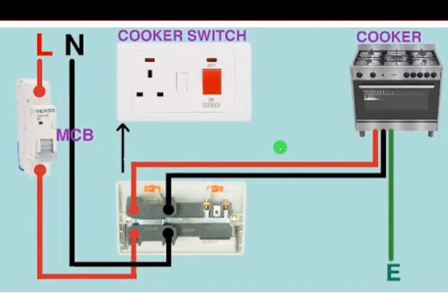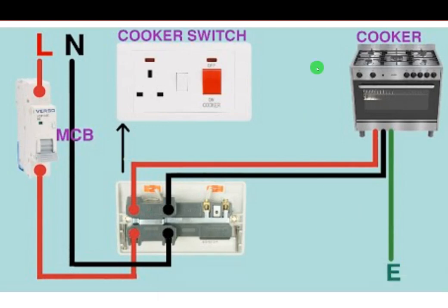Okay, so that is why the calculation is very simple. The 10 amps is because you use an additional auxiliary socket attached. Then the leftover current belongs to the cooker. All right, hope it's clear. So the 10 amps is for here, then the rest is for the cooker. That is judging by the calculation. I hope it's clear now. Okay, let's go back and finalize our calculation. All right.